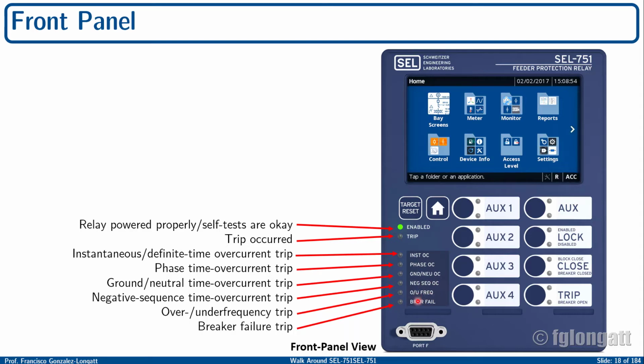Then we have over and under frequency and the very important breaker failure. It's typical that SEL relays have a front port for communication, called port F, typically an RS232 connector. In this case, the physical device we have at the lab is not equipped with the front connector because we are using an Ethernet connection at the back for connectivity, since we are interested in doing research on IEC 61850. If you allow me, I will switch the camera and go to the physical relay.